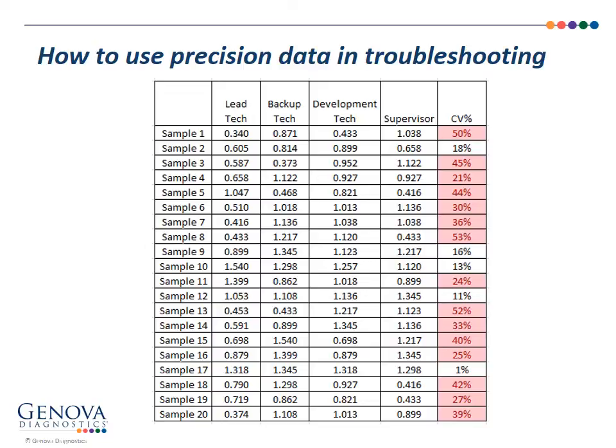And we tried to see, do any of these two match each other? And they didn't. If you remember the dartboards, when we were talking about the difference between precision and accuracy, this just smelled like a precision problem. If those CVs had all been 22 to 26%, still bad, but at least consistent, we might have questioned more of an accuracy issue. Like maybe something is pushing everything off by 22%. But in this case, it's all over the place. It's that first dartboard, where I'm just throwing darts everywhere. So we said, okay, we think we have a precision problem.